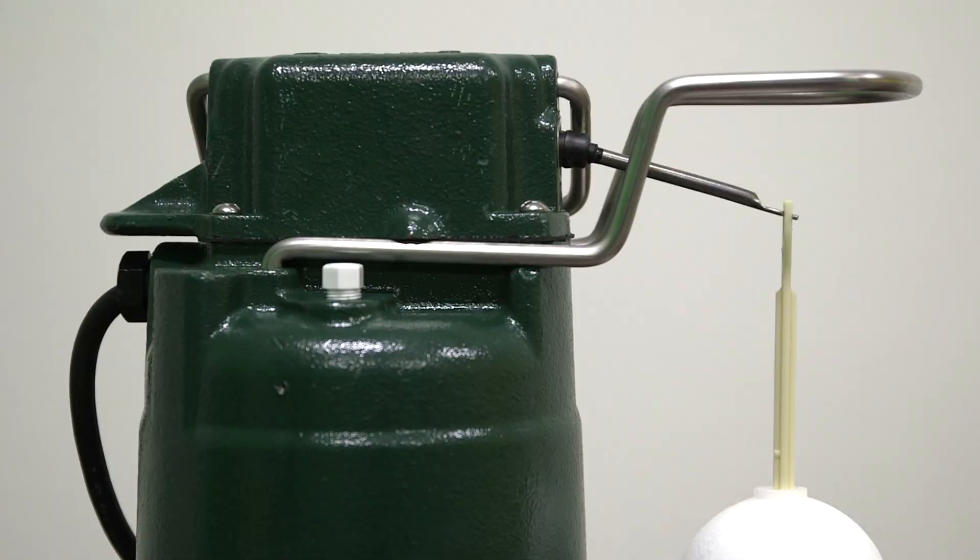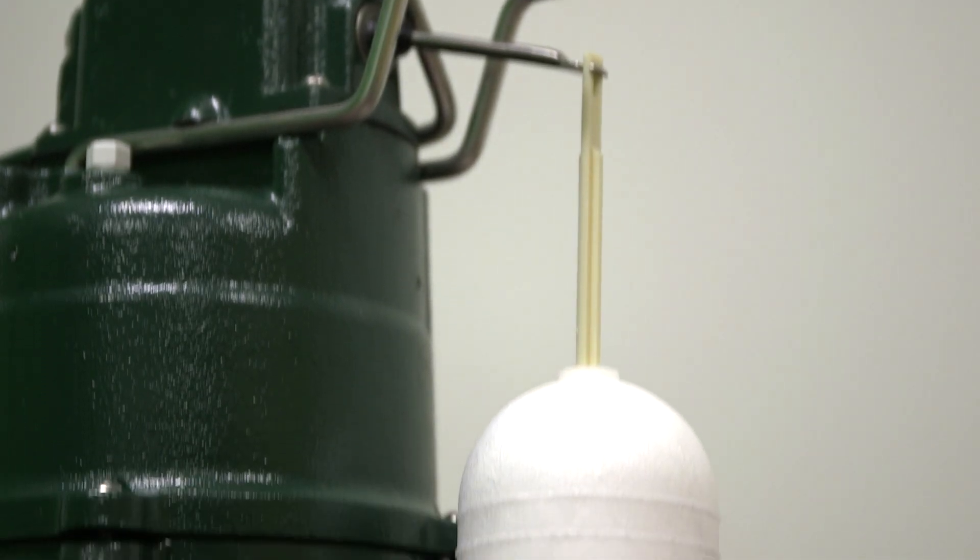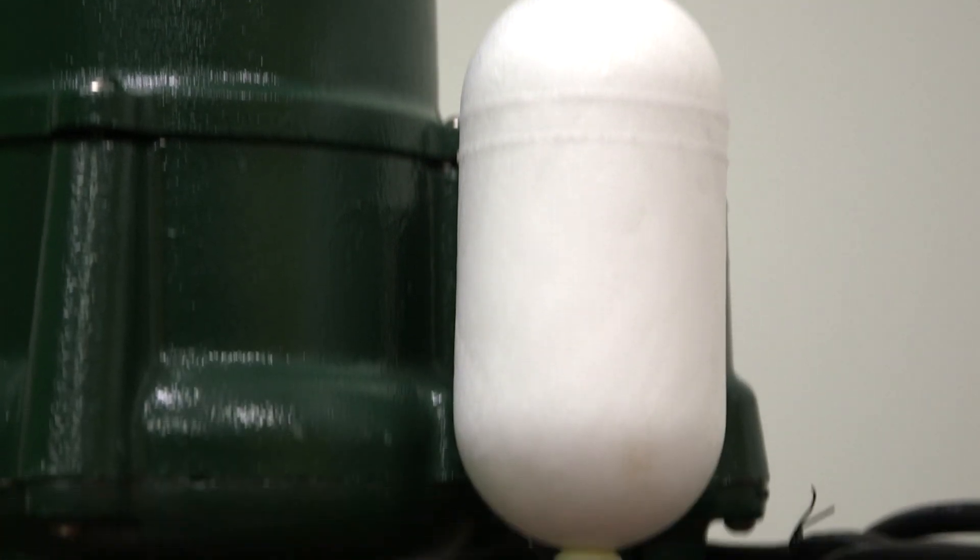This model includes a float operated two pole mechanical switch, a stainless steel float guard switch arm and a solid buoyant polypropylene float which prevents water from filling the float and causing malfunction.